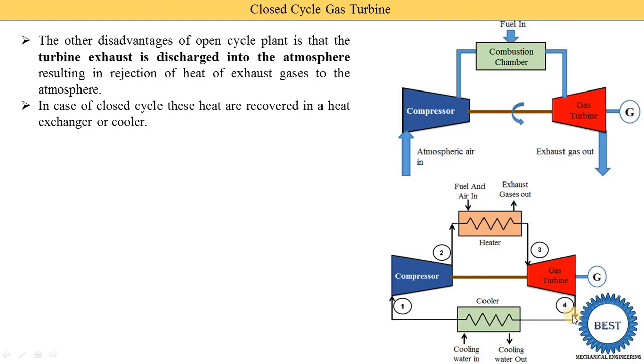After the turbine, we install one component called the cooler. It reduces the temperature of the exhaust working fluid coming out from the turbine. For reducing the temperature of the working fluid, cooling water is supplied in the cooler and then the cooling water exits. The working fluid coming out from the turbine is passed inside the tubes and the water is outside the tubes. Water absorbs the heat energy from the working substance, so the temperature of the working substance is reduced, and this working fluid is supplied to the compressor.